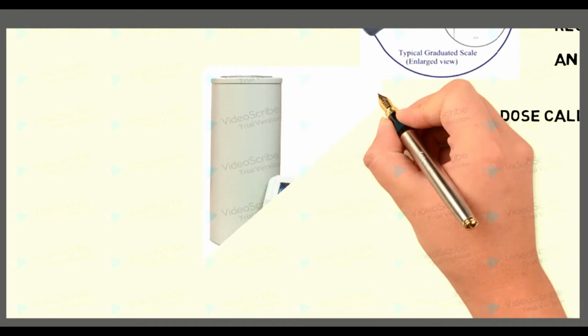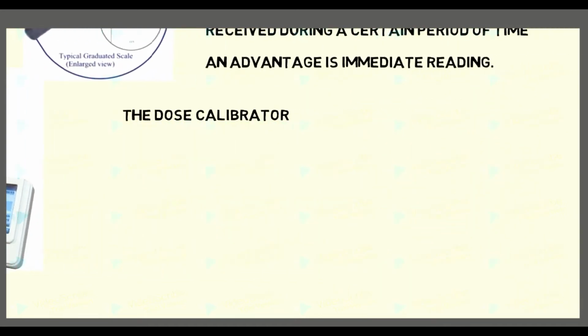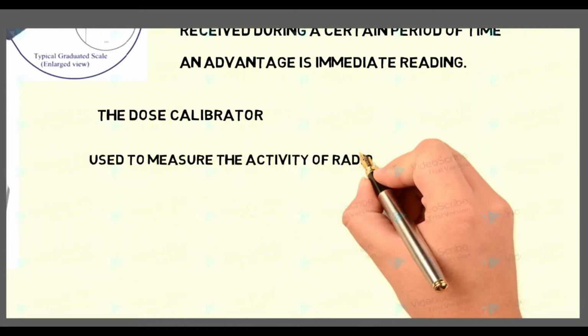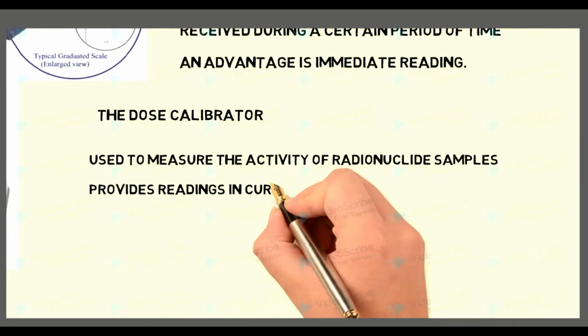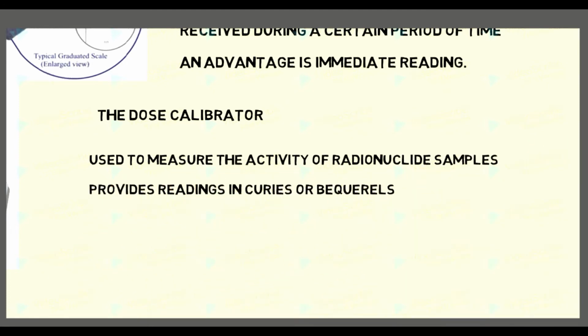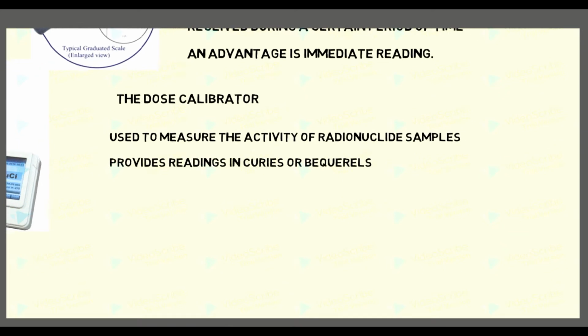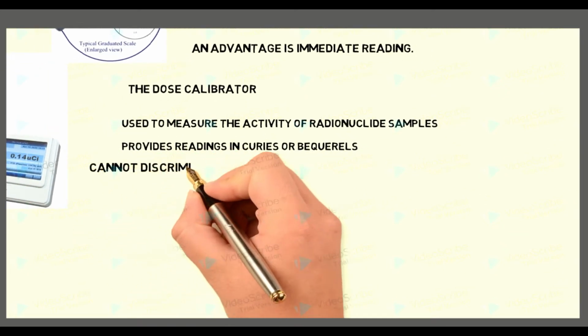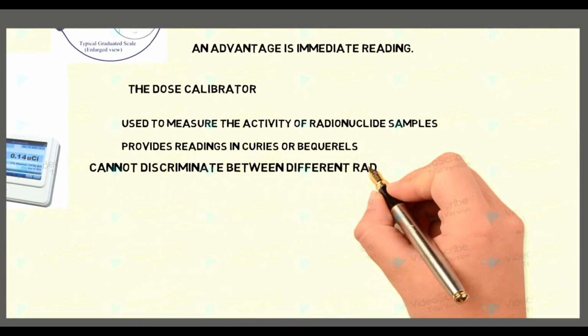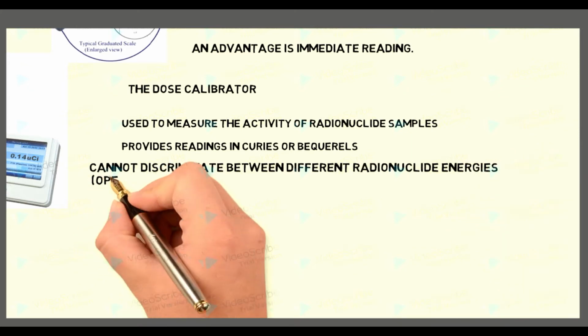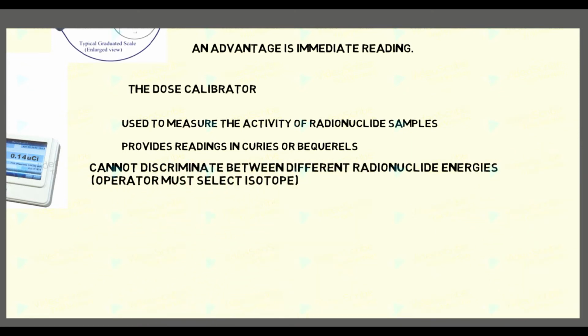The dose calibrator. The dose calibrator is used to measure the activity of radionuclide samples, and it provides readings in curies or becquerels. It cannot discriminate between different radionuclide energies, so the operator must select the isotope.